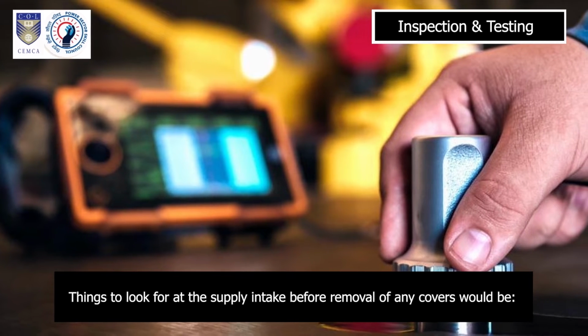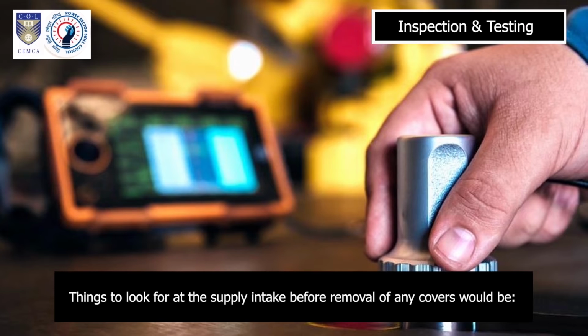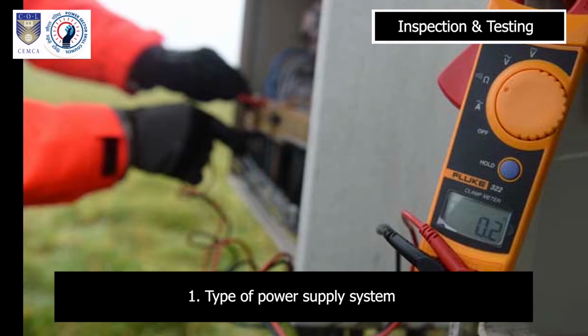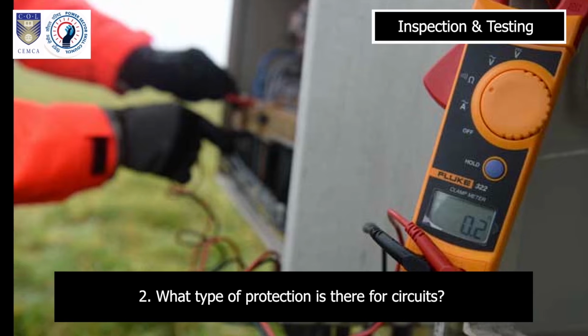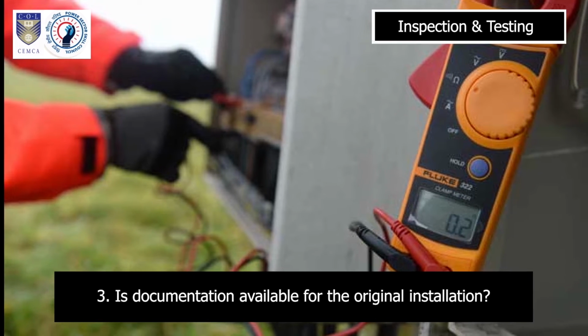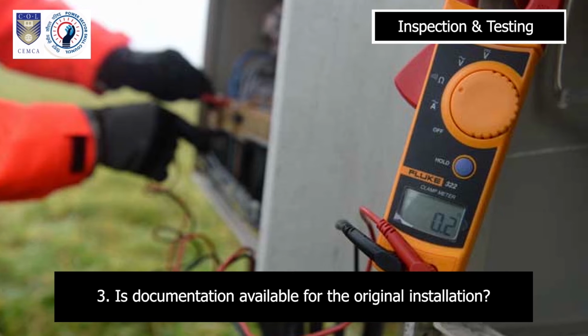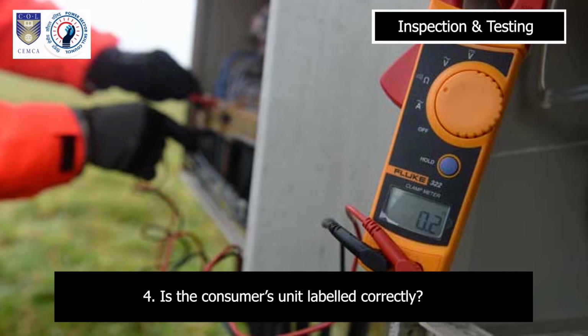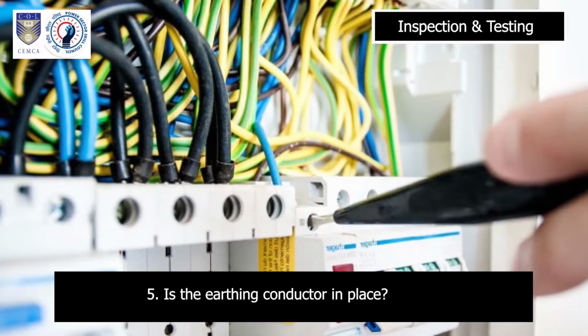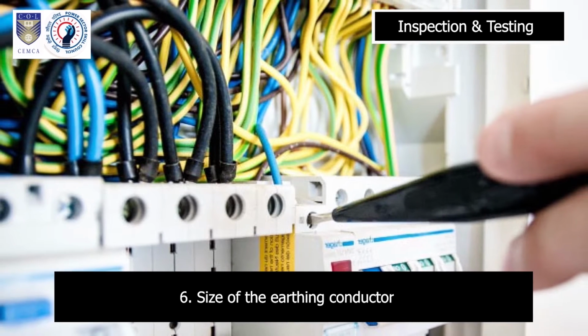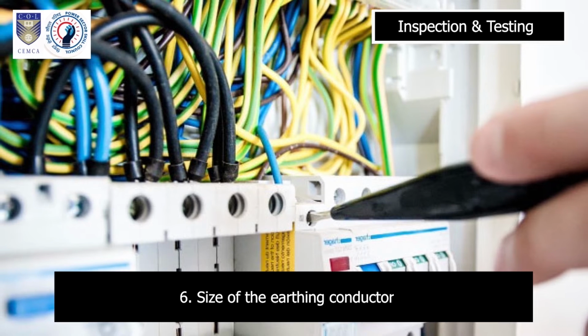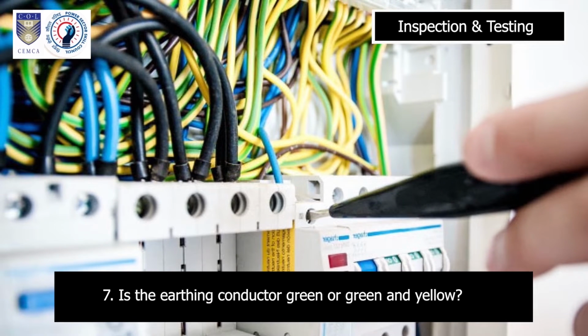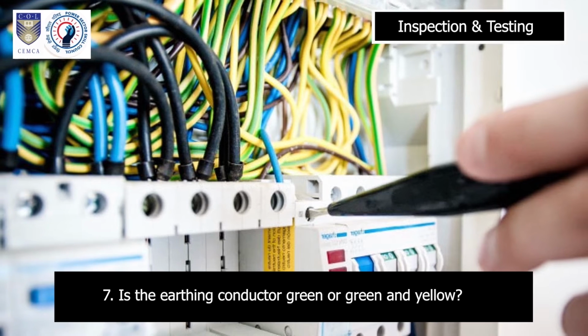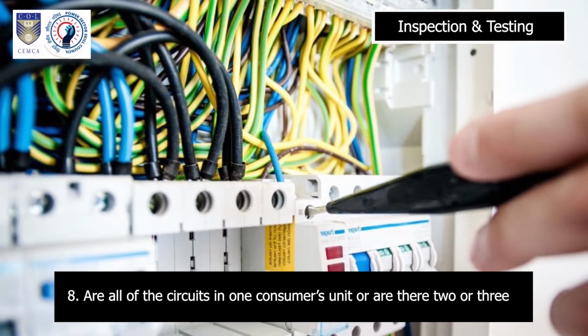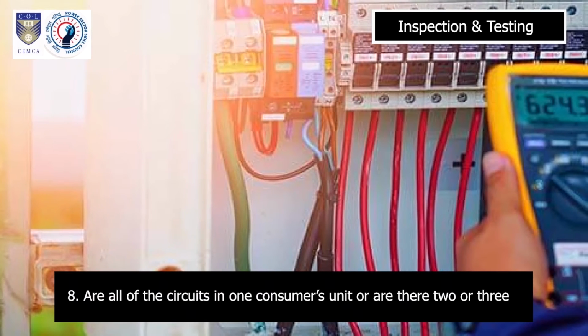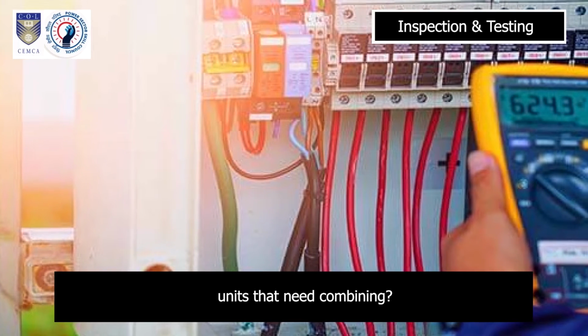Things to look for at the supply intake before removal of any covers would be: 1. Type of power supply system. 2. What type of protection is there for circuits? 3. Is documentation available for the original installation? 4. Is the consumer's unit labeled correctly? 5. Is the earthing conductor in place? 6. Size of the earthing conductor. 7. Is the earthing conductor green or green and yellow? 8. Are all of the circuits in one consumer's unit, or are there 2 or 3 units that need combining?